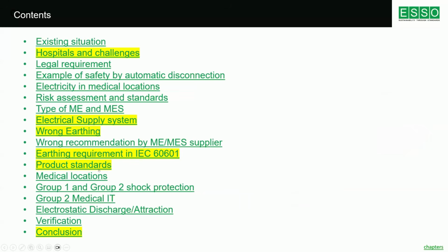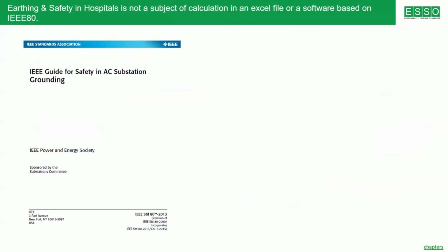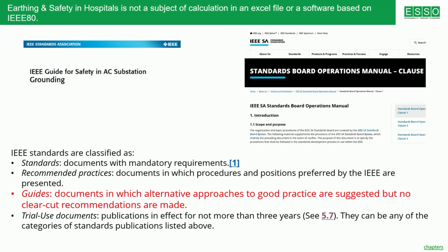There are requirements in the product standard. So earthing is a subject which is related to all these subjects. It is not about making an Excel sheet, a calculation of fault current, assumed fault current. Sometimes I'm so surprised that people are not even able to understand the difference between symmetrical short circuit current between phases and earth fault current. 50 kiloampere, that is a symmetrical short circuit current. It has nothing to do with the earth fault current. But the whole design people wanted to make for 50 kiloampere, 65 kiloampere, and always based on IEEE 80 standard.